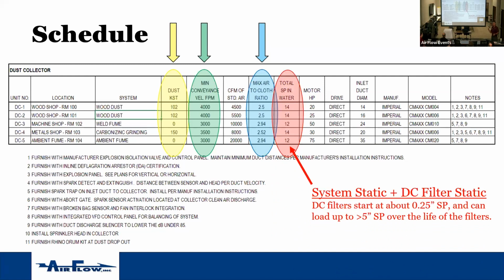And then your static pressure. Everyone likes to put total static pressure on the schedules, totally fine. But total static in a lot of cases might not pick up the equipment itself. So we have to make sure we pick up the static pressure from the collector itself.